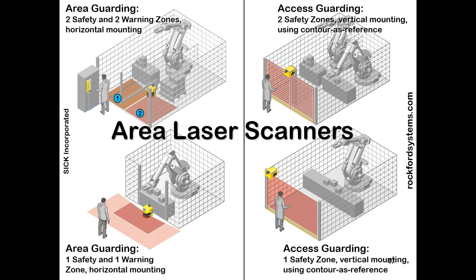The light shading is a warning zone. The dark shading is a fault zone. You step inside the warning zone, you slow the robot down to creep speed, flash a light, beep a horn. If the operator keeps walking into the fault zone, it sends a stop signal to the guarded machine. Now, those zones, the warning zone and the fault zone, are both programmable as far as their size and shape. You can program that right out on the shop floor with a laptop computer.